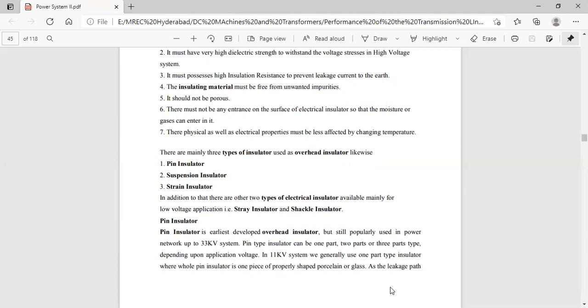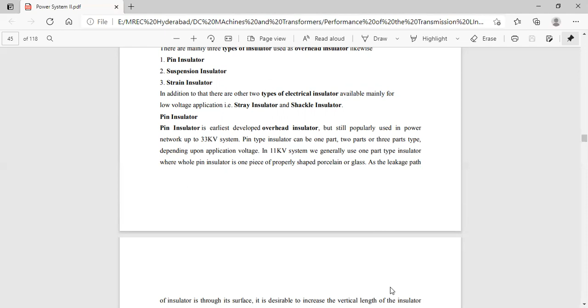The first one is the pin insulator. The pin insulator is the earliest developed overhead insulator, but it is still popularly used in power networks up to 33 kilovolt systems. Pin type insulators can be one part, two parts, or three parts type, depending upon application voltage. In an 11 kV system, we generally use the one part type insulator, where the whole pin insulator is one piece of properly shaped porcelain or glass.